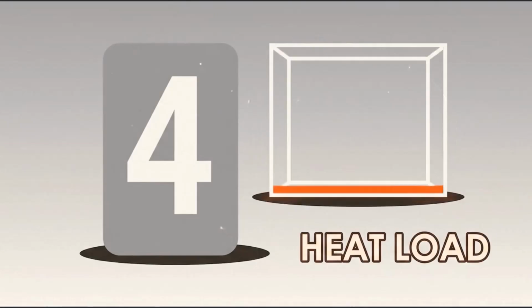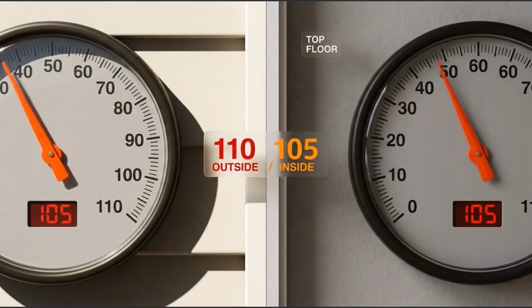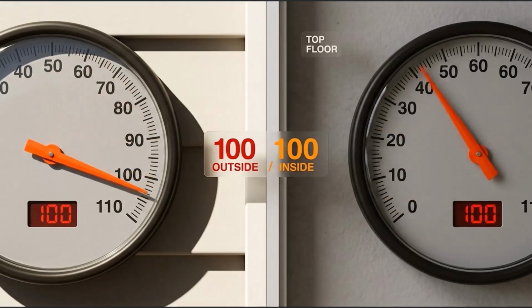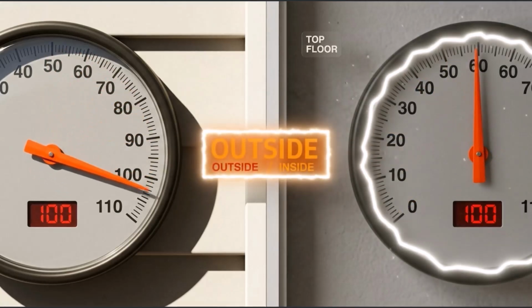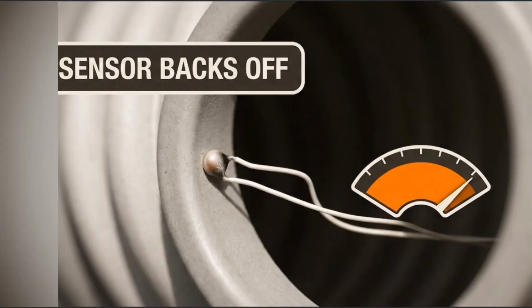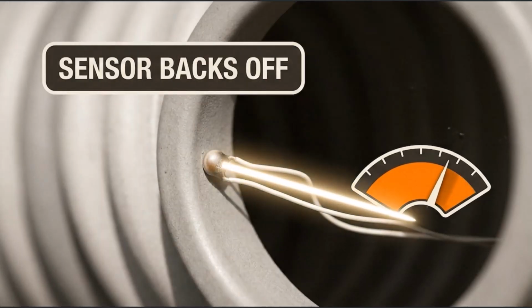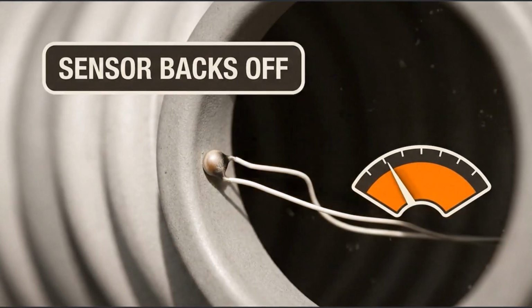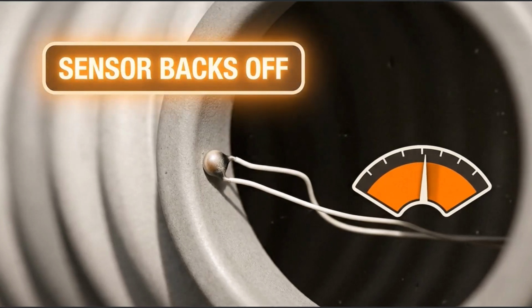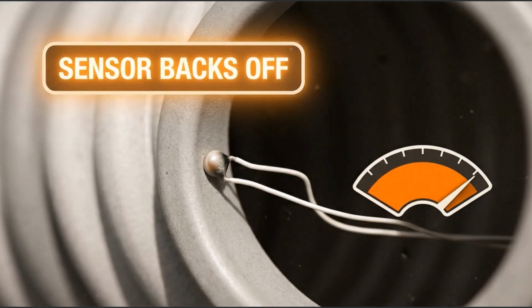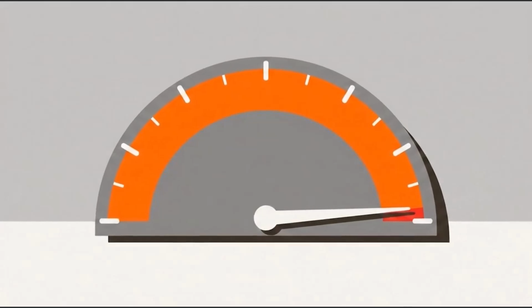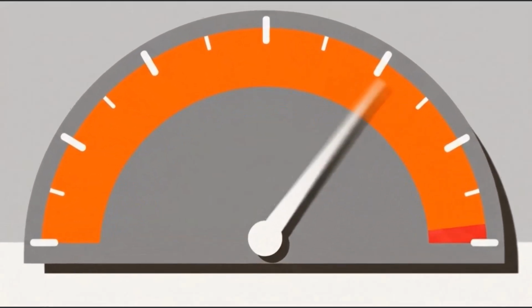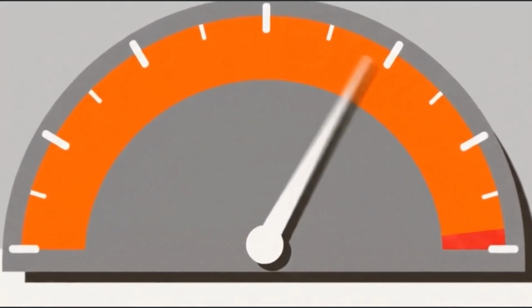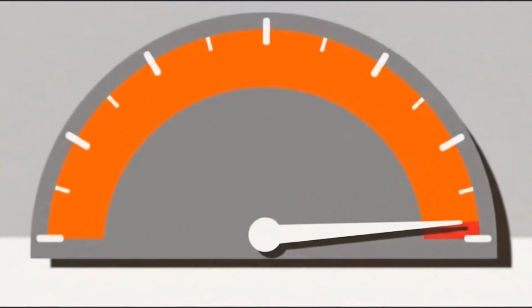Number 4, the heat load of the room. 110 degrees outside, top floor, afternoon sun straight through the window, 105 inside the room. In that situation, the inverter's sensor sees the room cooling down, so it starts backing off its own speed, while you still need full power. The fixed speed machine is stupidly good right here. It does not even know how to back off. It just runs at 100.